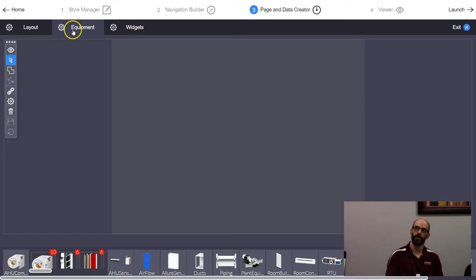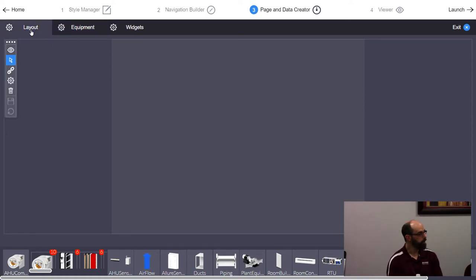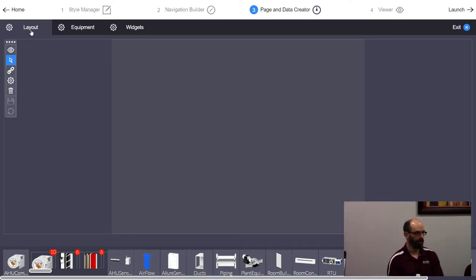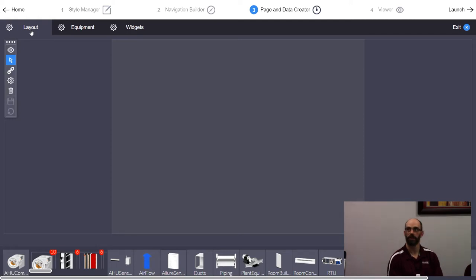It always defaults to the Equipment layer. Go back to Layout first. There are three layers: Layout is where you put piping, ductwork — things that don't move and won't be animated — the static part. Equipment is where you put the heating coil, cooling coil, fan, dampers — things that move. Widgets is for text, updating values, thermostat interface, trends, and graphs.